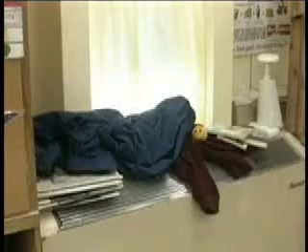Is air flowing into and out of the room as designed? If not, the occupants will not have access to the fresh air that they should be getting on a regular basis. Check the supply and exhaust vents and be sure that they are all free from blockage or obstruction. Oftentimes you'll find books and coats on top of a unit ventilator in a classroom. This practice should be discouraged.